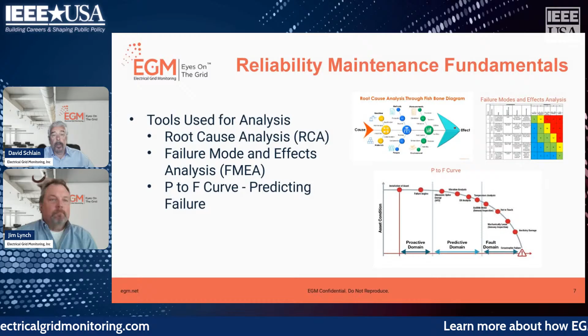I'll give you an example. If you start seeing these disturbances increasing in frequency and correlated with wind, you can get a good idea it's trees rubbing on a line. And if you have an electrical signature of a waveform that really replicates the characteristics of tree encroachment, then you're starting to get a fuller picture. So that P to F curve and the predictability is becoming a reality.